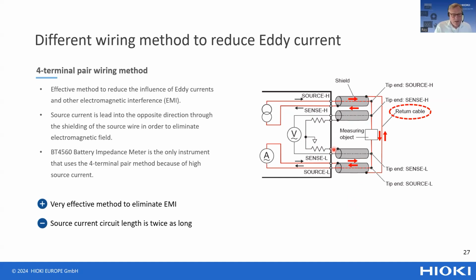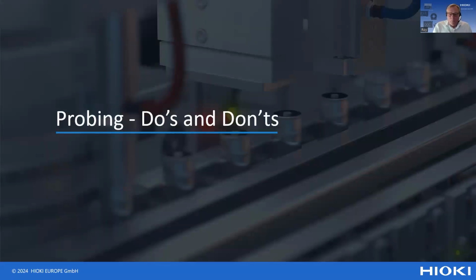So this method even eliminates the electromagnetic interference better than the 4-wire method, but there is also a disadvantage to this technology. Because we are sending the source signal twice through the wiring, the length of the wiring is twice as long as we normally have with the 4-wire method. Therefore, when you use the BT4560 in your production line, it is even more important to make sure that the measuring instrument is closely located to the battery that you want to test. So, besides wiring, the way of probing of a battery can influence the accuracy and the reproducibility of the measurement result.